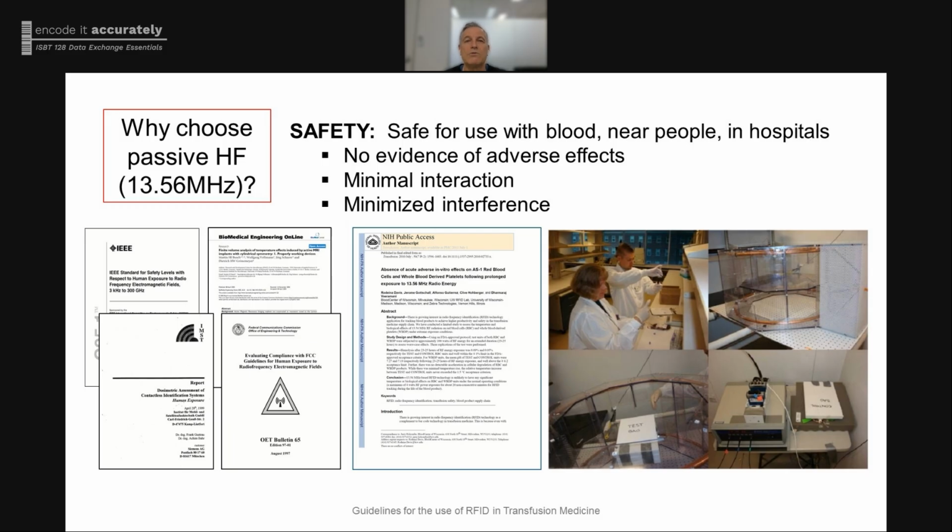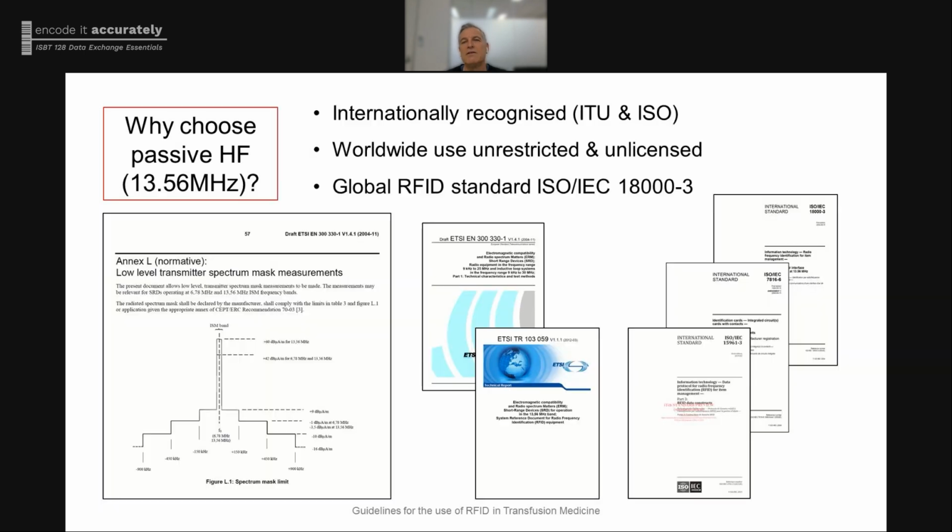On the basis of these results, the FDA has granted permission to proceed with the use of HF RFID for transfusible blood products. Basically, HF radio energy was shown to be safe and not absorbed nor interact significantly with water, ice, biological, or living systems. Furthermore, the HF reader field can be designed to minimize radio emissions, to minimize interference with other medical devices.